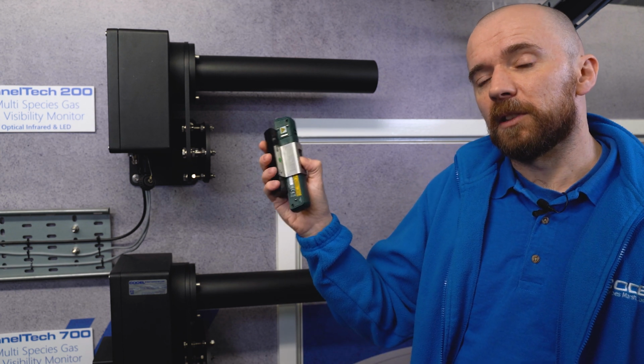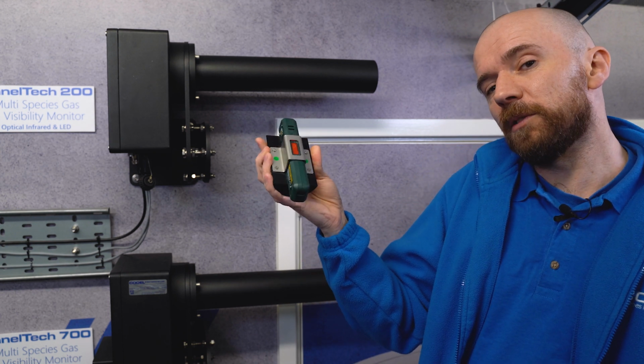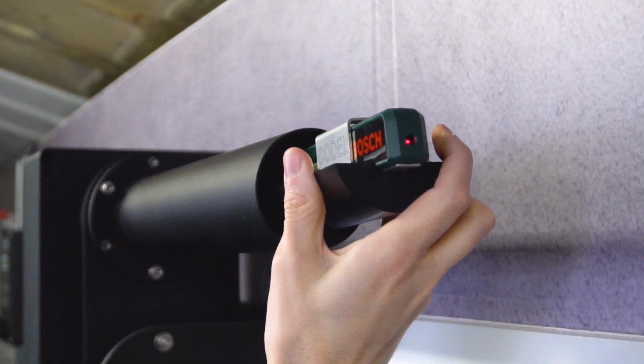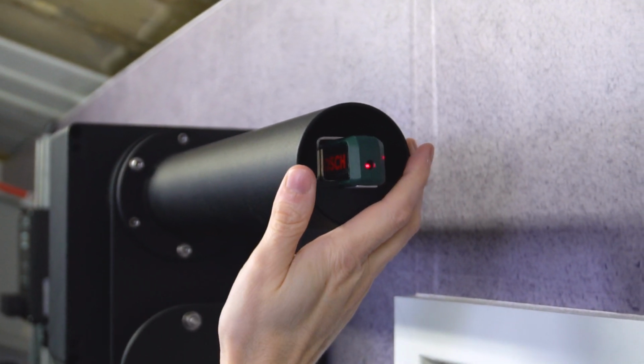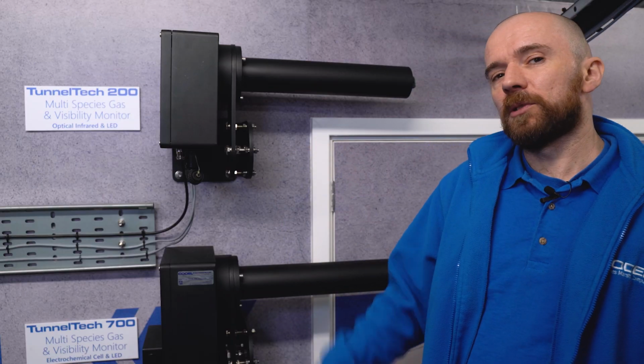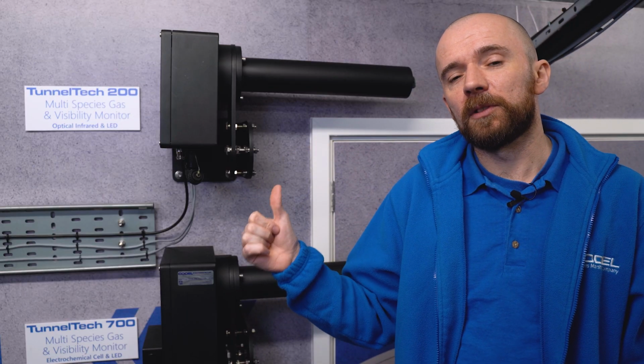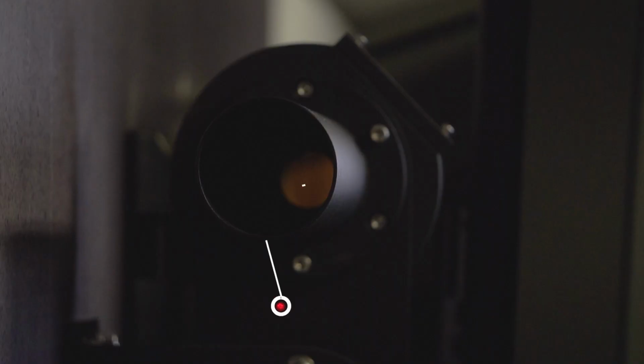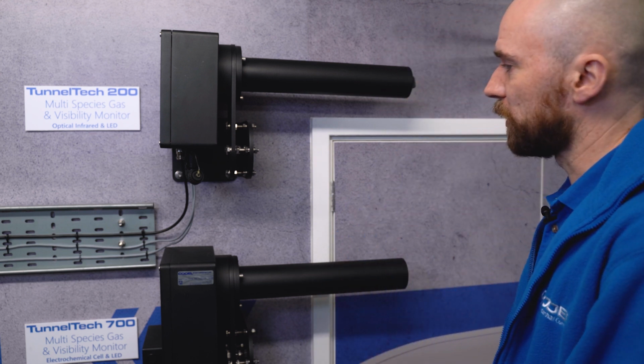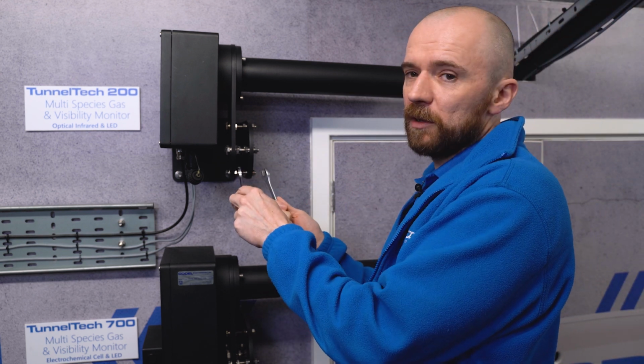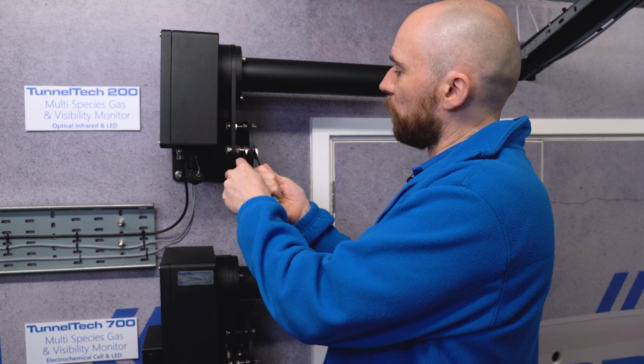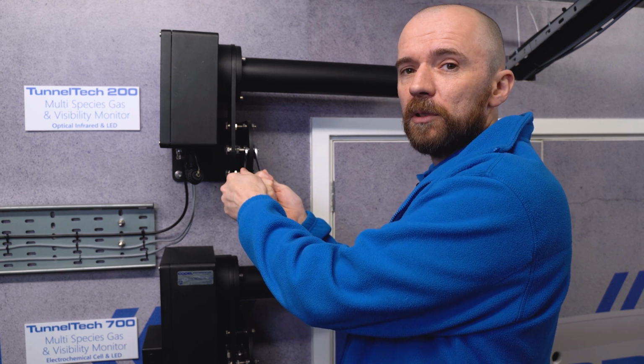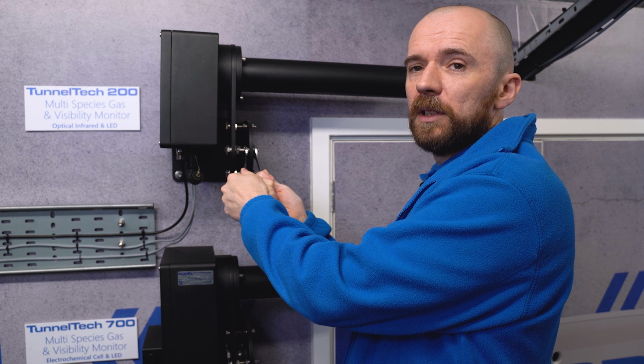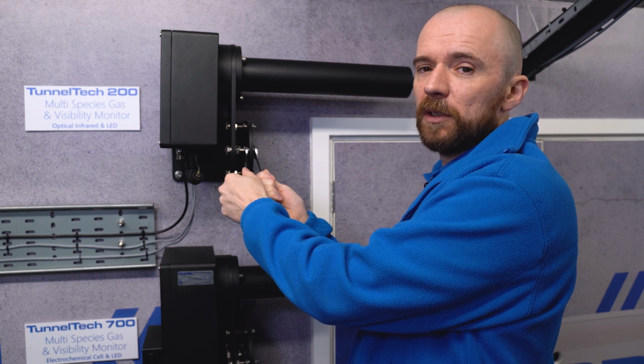The first stage of the process, the coarse adjustment, utilizes the laser tool. So first of all, we turn it on, insert it into the sight tube facing the mirror. With the alignment tool situated, the aim of this part of the process is to point the laser at the mirror on the other end of the bracket. We do this by adjusting the alignment studs using our 13mm spanners, one plane at a time. So first we would do the horizontal, then after completing the horizontal, we do the vertical.